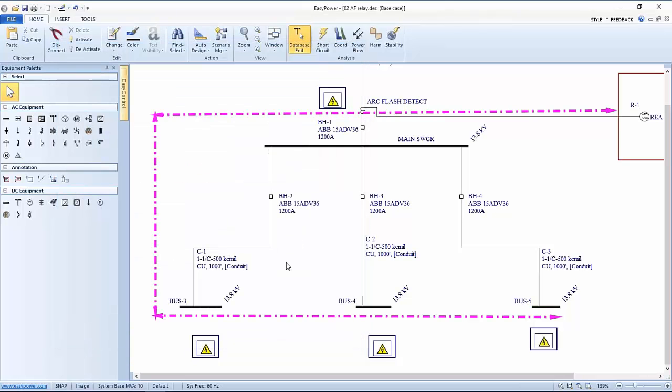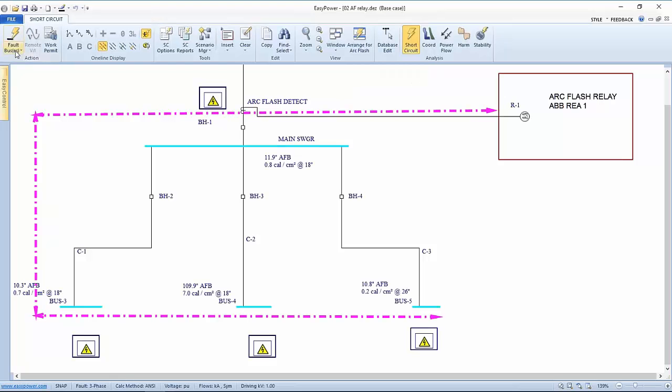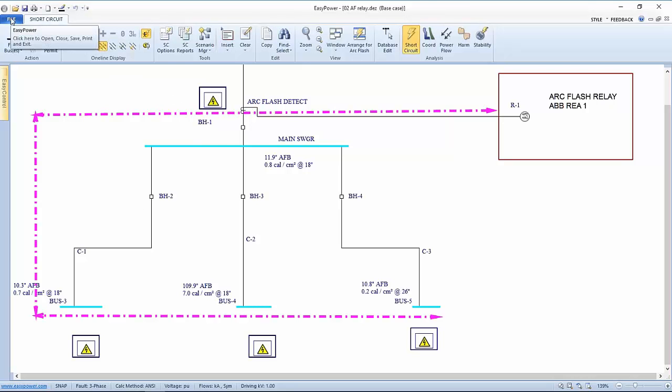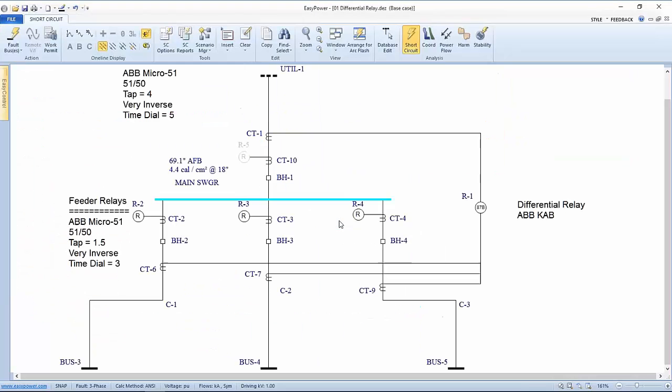These are very fast. And when I go into my Short Circuit Focus now and I fault my buses, we can see that a system that has relatively high current has very quick reaction time to an Arc Flash event and consequently relatively safe settings for workers that have to be in the area. I think you got the idea for how to set up these fixed time devices.